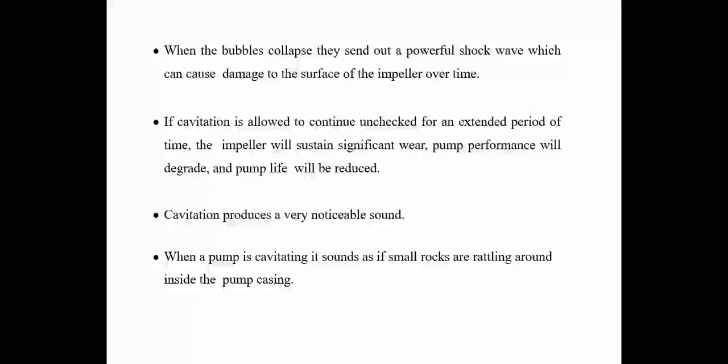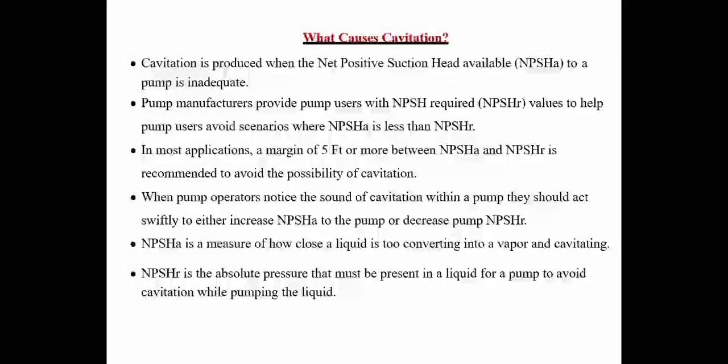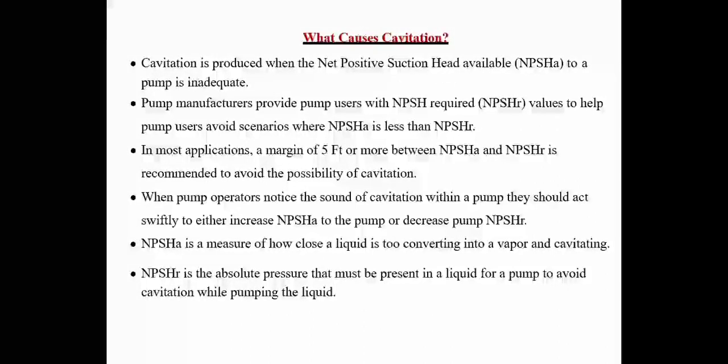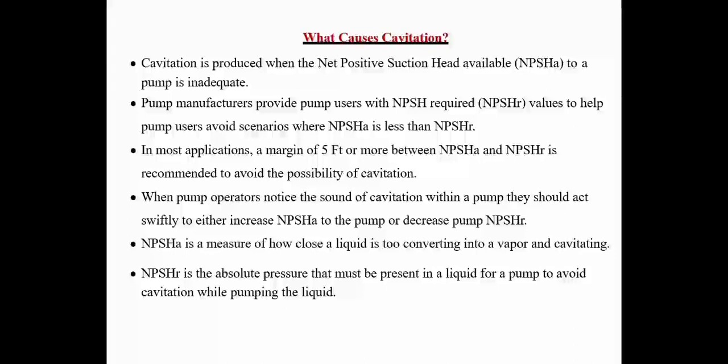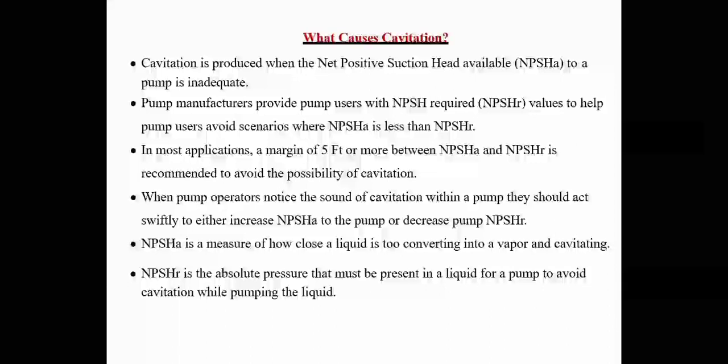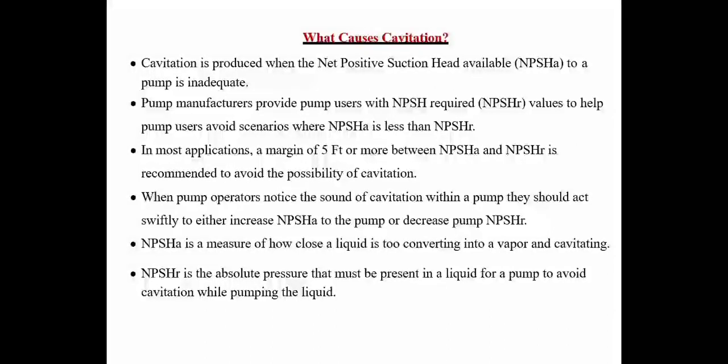And why does this process occur? What causes cavitation? I have already explained this. When the net positive suction head available at the inlet of the impeller is much less than the net positive suction head actually required for the movement of water, cavitation occurs. Air bubbles enter, the air bubbles burst, and the sound is produced.